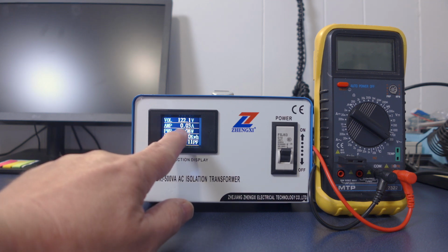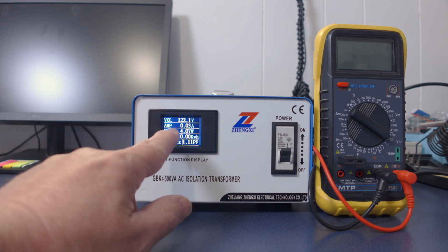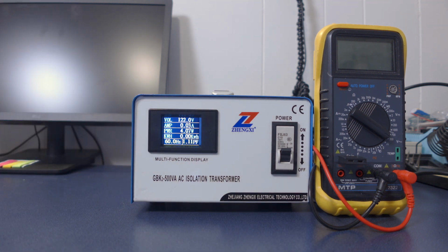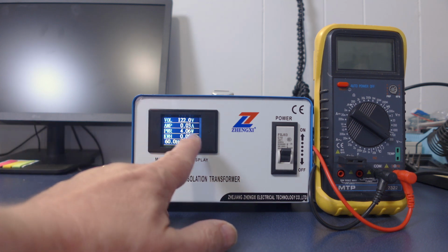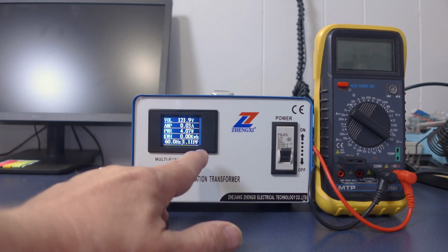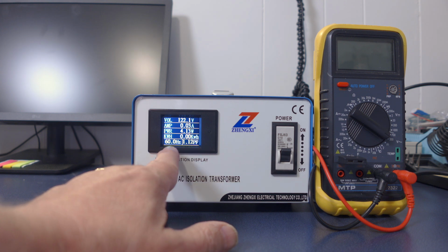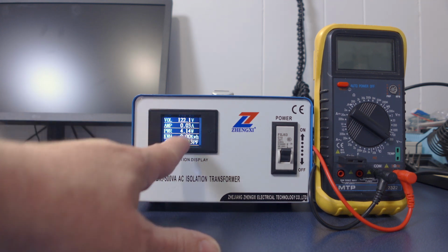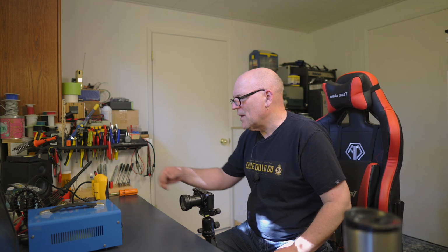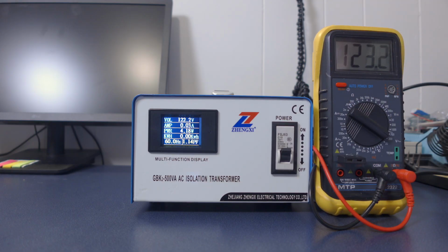It's drawing 0.03 amps. Not really any significant draw there. It's just what the unit itself is drawing. Shows us the power consumption. It shows us power factor and shows us the line frequency. So we basically have 122 volts coming in at 60 hertz, which is what we should expect in North America. Are we getting any voltage on the outputs? Let's have a look. It says we're getting 123.2, so not an exact one-to-one transformer in here, but a volt, half a volt higher on the output is kind of to be expected when you're running through a transformer.